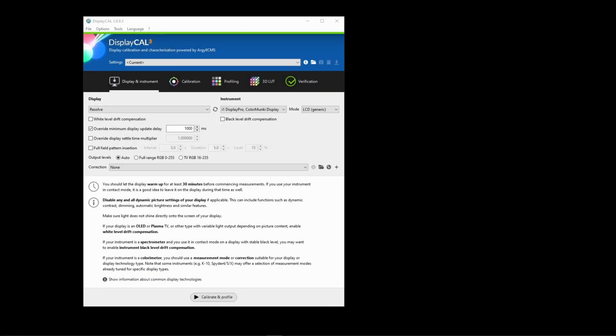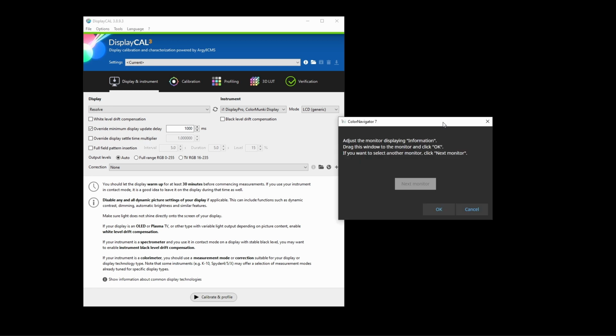DisplayCal doesn't communicate directly with the EIZO monitor, so therefore it doesn't have access to the internal test pattern generator or the internal probe, and you can't directly upload a LUT from DisplayCal. So to do that, what we need to do is actually use a combination of DisplayCal with Navigator 7. Navigator 7 being the free software that comes available with the CG series EIZO monitors. And what that allows us to do is we need to go and calibrate the CG319 first to be able to upload a 3D LUT.